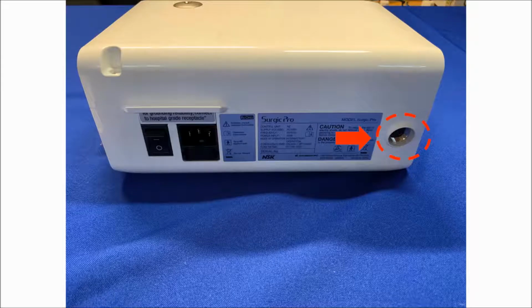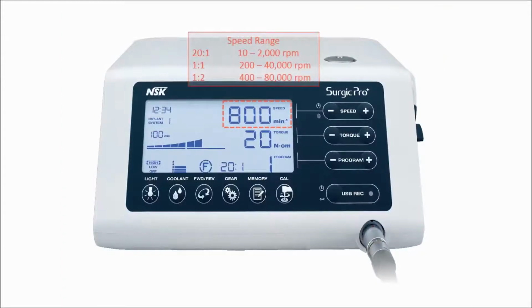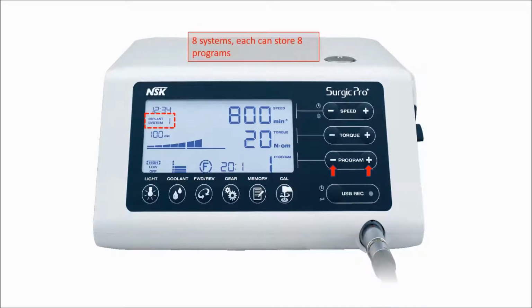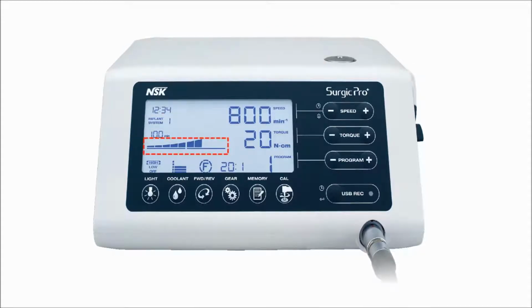Let's talk about the LCD display and how the buttons work. Speed, depending on the attachment, can be changed with plus and minus to set the maximum speed. Implant system number goes from 1 through 8. You press plus or minus at the same time. Torque graph: this displays the amount of bone resistance applied to the drill. Torque, somewhere between 0 to 80 Newton centimeter for implant. You can change it by pressing the plus or minus button.